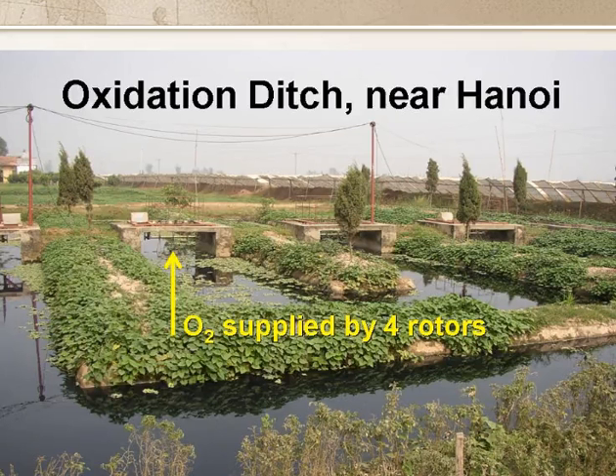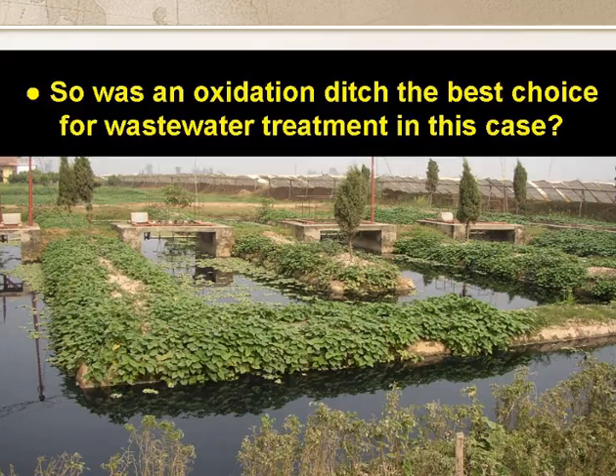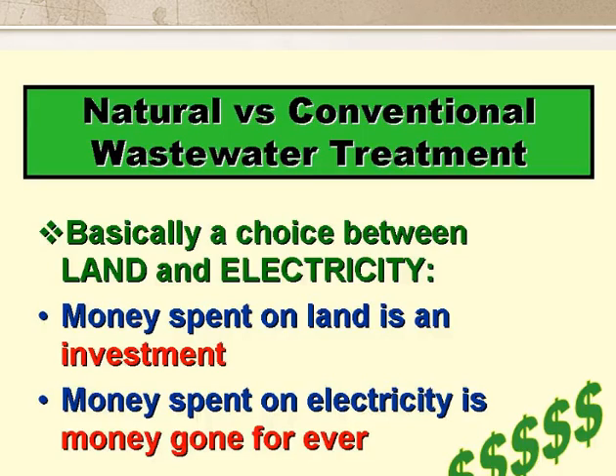This slide shows an oxidation ditch serving a small town near Hanoi in Vietnam. The oxygen required for BOD removal is supplied by four rotors, but the installed power was only 2 kW, and the power is not normally switched on. This is actually quite common as the local authority can't afford to pay the electricity bill. So we have to ask: was an oxidation ditch the best choice in this case? The answer is a resounding no. When comparing natural wastewater treatment in ponds with conventional electromechanical treatment such as activated sludge, the choice really boils down to a choice between land and electricity.